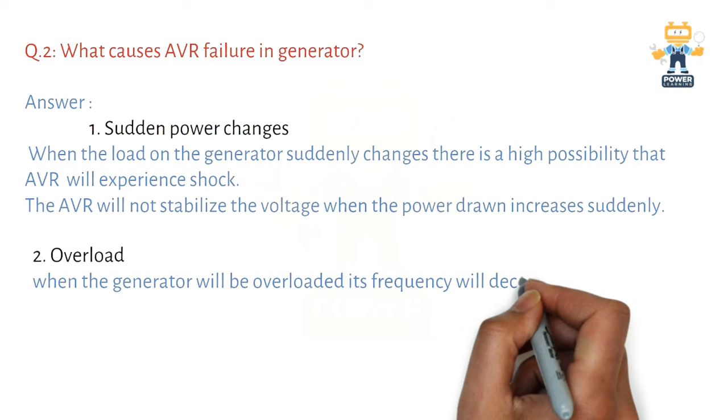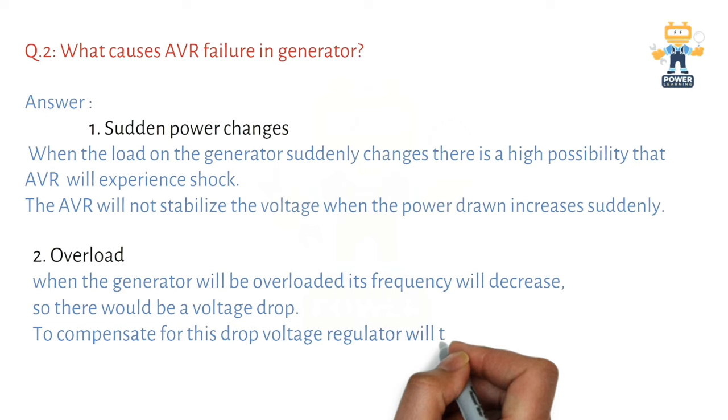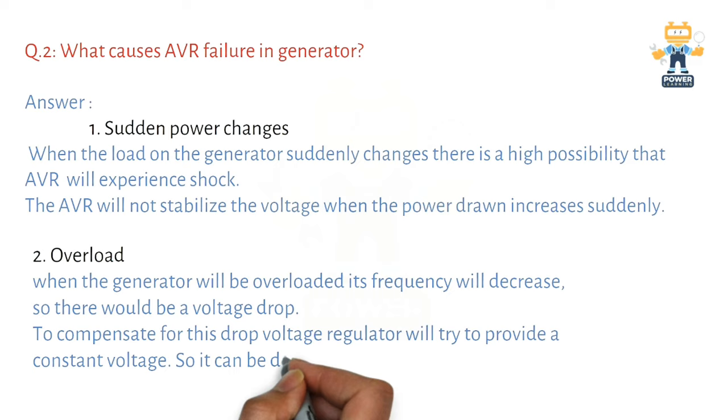Cause number two: Overload. When the generator is overloaded, its frequency will decrease, so there would be a voltage drop. To compensate for this drop, the voltage regulator will try to provide constant voltage, so it can be damaged. Avoid overloading.